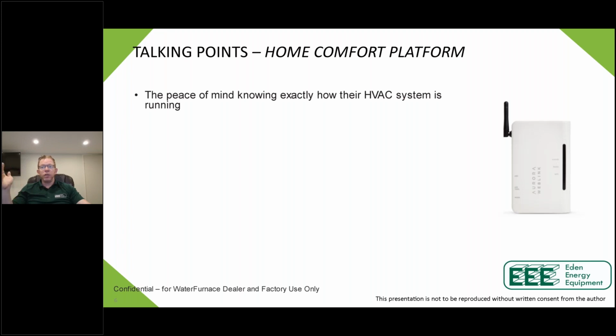Depending on the unit you have, that can be as detailed as superheat, subcooling, suction pressure, discharge pressure — every input, every output, every contact in that unit. You can see exactly what it's doing every 10 seconds, going back over 18 months. As a service technician, that's amazing. It makes it very easy for us to troubleshoot the equipment.